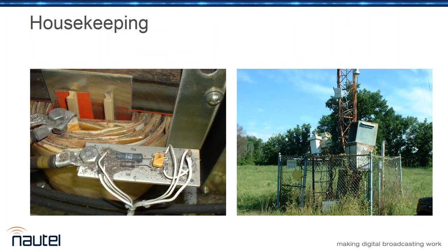Definitely clean the dust out of it. As you can tell in this particular picture from the rust on the choke, this is a fairly humid site. This whole non-condensing humidity thing just doesn't apply in this particular location. So when you have a whole bunch of dirt on things, plus a whole bunch of humidity, you've got something that could potentially be conductive. At that point, you can end up having more problems than you're trying to avoid.